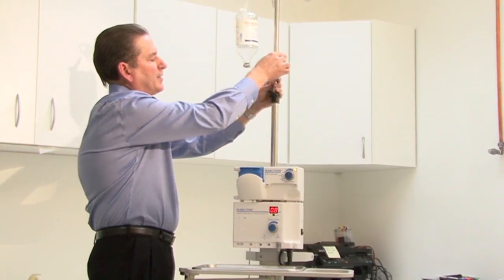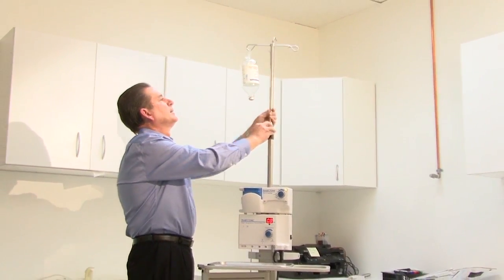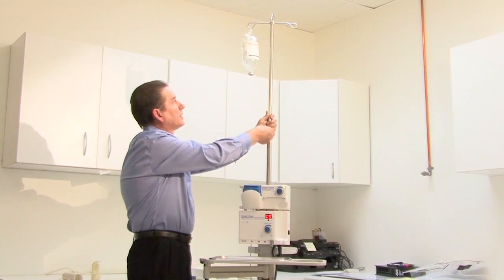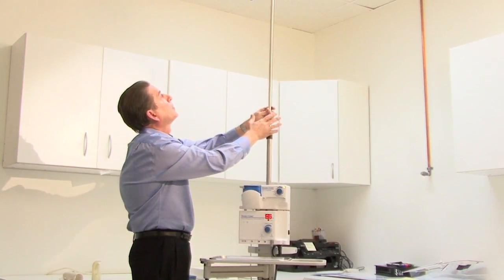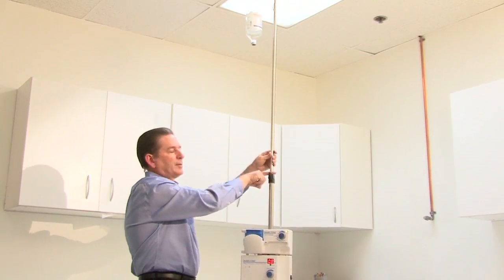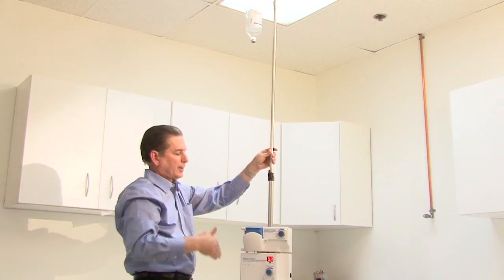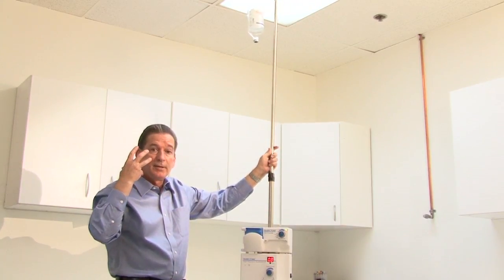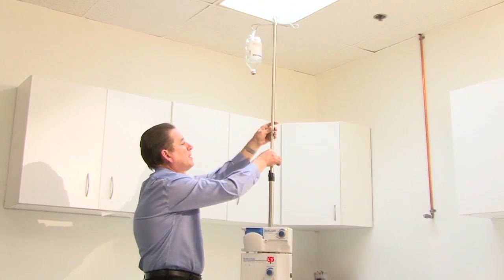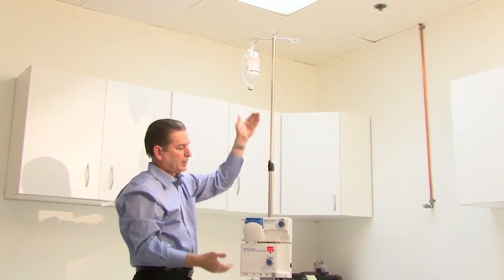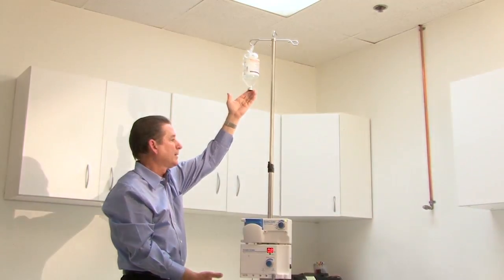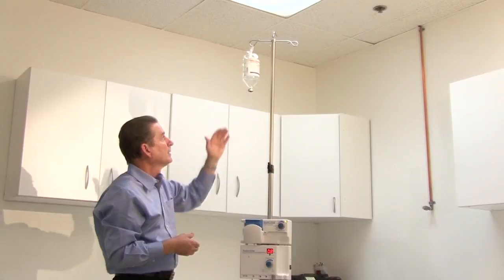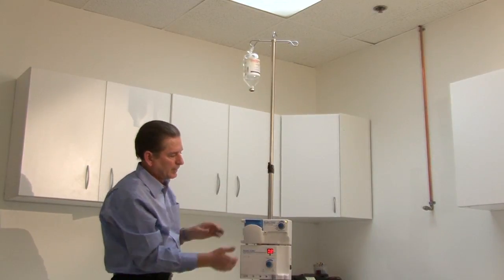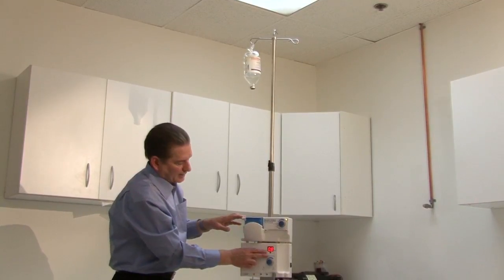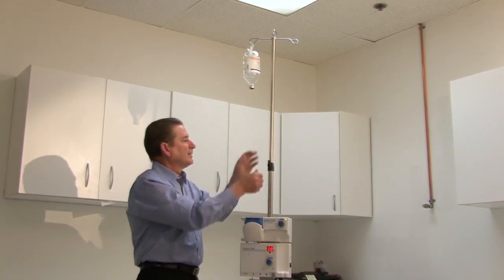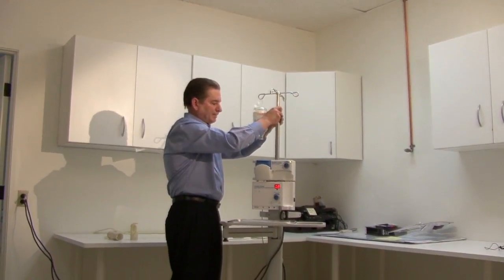Irrigation is just provided as it would be with cataract surgery from a bottle of BSS that's elevated to pressurize the eye. And if you look at the pole, the maximum height, the pole will actually stop. And some surgeons actually like to operate at a very high bottle height because it just pressurizes the anterior chamber during the procedure. But the most common setting is to set the bottle height about 3/4, and this is about 80 to 100 centimeters of bottle height. That's very typical for the trabectome procedure. So that gives a nice pressurization of the anterior chamber, the gentle outflow of about 3 mils a minute, and a surgical energy setting of about 0.8 watts. So those are the typical settings for the equipment system.